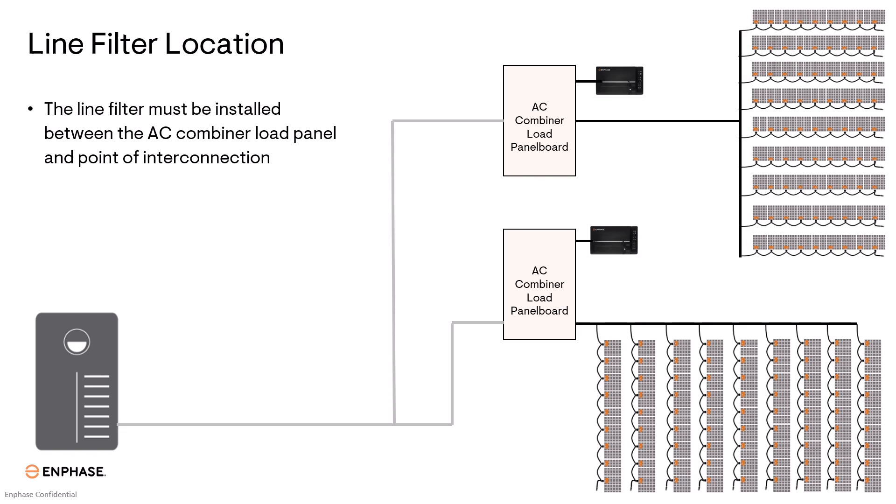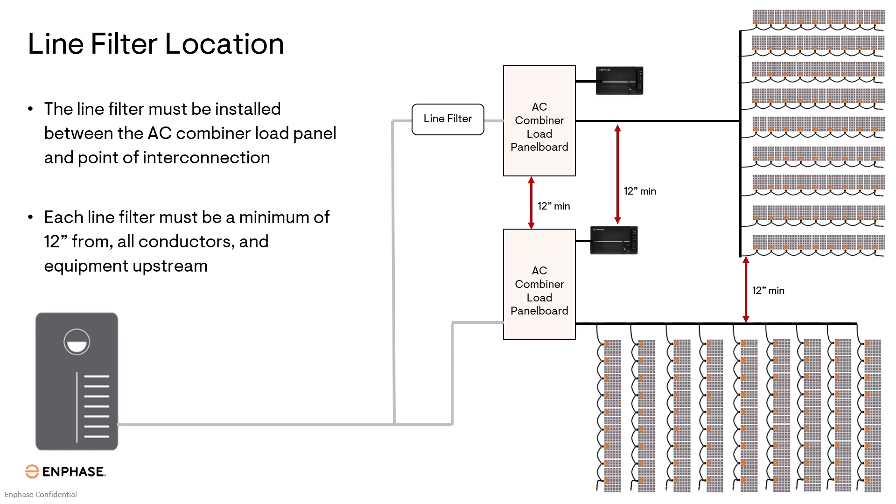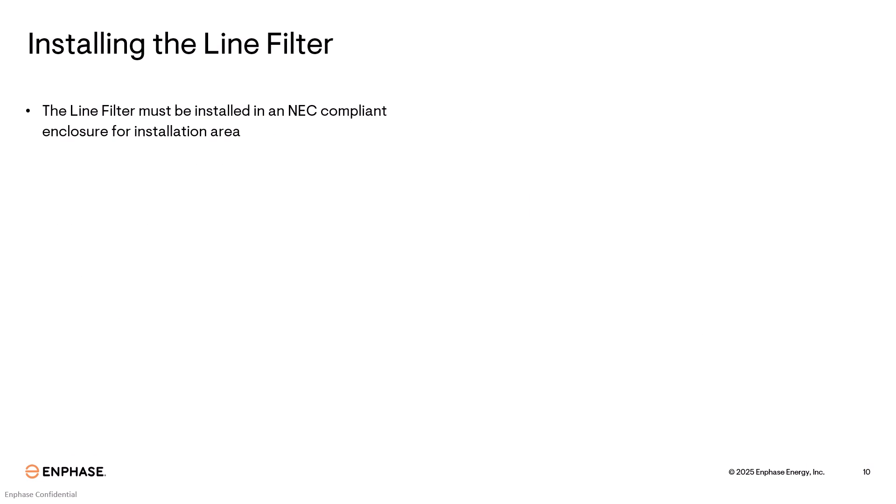Line filter must be installed between the AC combiner load panel and point of interconnection. Each line filter must be a minimum of 12 inches from all conductors and equipment upstream from the line filter. The line filter must be installed in an NEC compliant enclosure for the installation area.